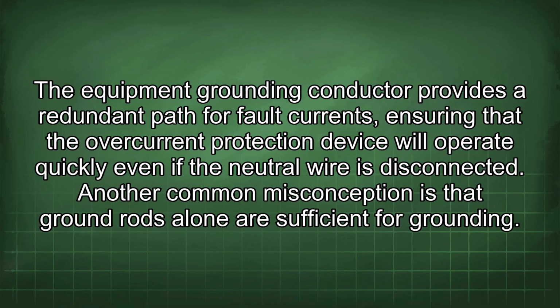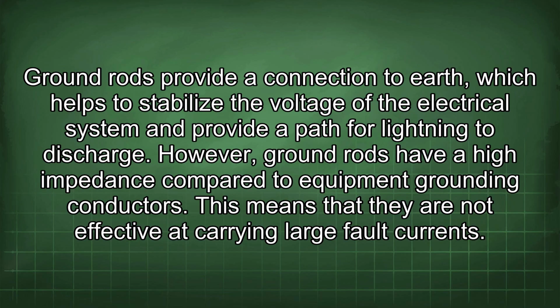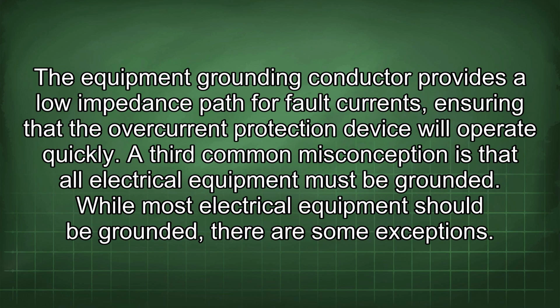Another common misconception is that ground rods alone are sufficient for grounding. Ground rods provide a connection to earth, which helps to stabilize the voltage of the electrical system and provide a path for lightning to discharge. However, ground rods have a high impedance compared to equipment grounding conductors. This means that they are not effective at carrying large fault currents. The equipment grounding conductor provides a low impedance path for fault currents, ensuring that the overcurrent protection device will operate quickly. A third common misconception is that all electrical equipment must be grounded.